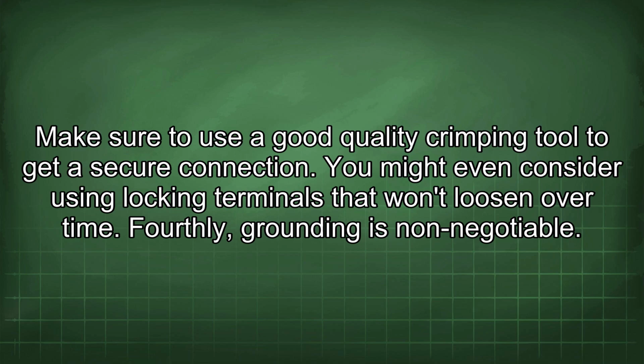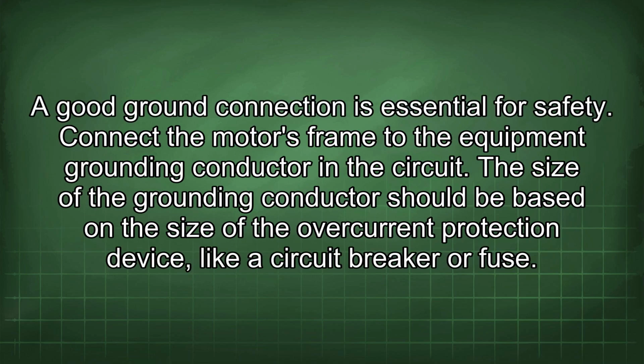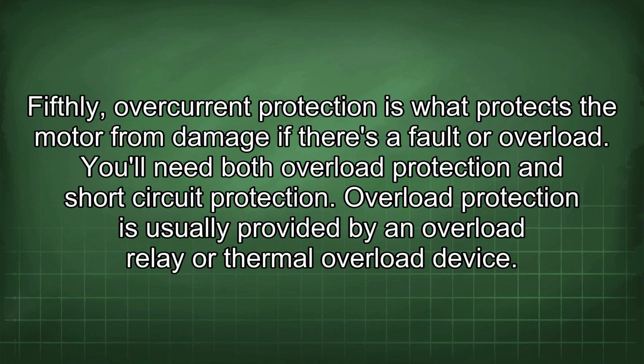Fourthly, grounding is non-negotiable. A good ground connection is essential for safety. Connect the motor's frame to the equipment grounding conductor in the circuit. The size of the grounding conductor should be based on the size of the overcurrent protection device, like a circuit breaker or fuse. Fifthly, overcurrent protection is what protects the motor from damage if there's a fault or overload.